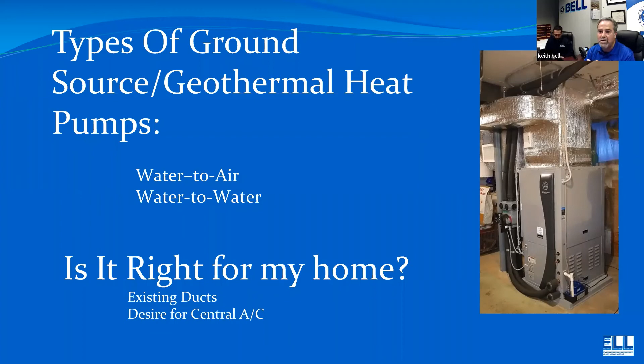And the water to water, essentially, well, here's an example here. This is how the pipes go down, and you reject the heat and then you accept the heat. And one added benefit for a geothermal system, they have a thing called the de-superheater. So when it's actually running, it can give you warm water. In the summer, you're getting free hot water. In the winter, you're getting a little bit of capacity off your unit to give you hot water. So it provides not all of your hot water, but it gives you an added benefit of getting hot water created from your geothermal system.